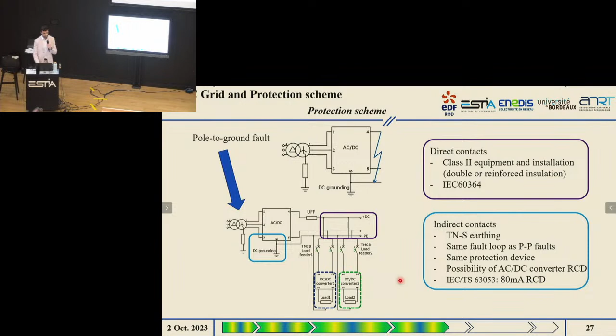And the second type of pole-to-ground faults concerns indirect contacts, which are often represented by insulation faults at equipment level. From our perspective, once again, the best way to protect the system from it is to use a TNS earthing system, because with this earthing system, pole-to-ground faults behave similarly to pole-to-pole faults, meaning that we could use the same protection devices here once again. And in order to increase the protection level against pole-to-ground faults, we could also imagine a function similar to a residual current device operated by the main AC-DC converter, comparing, for example, the measurements of the positive and the negative pole in order to recreate this RCD function.